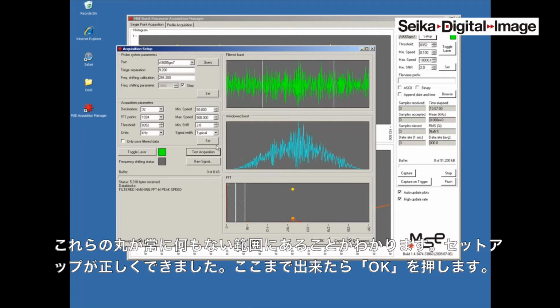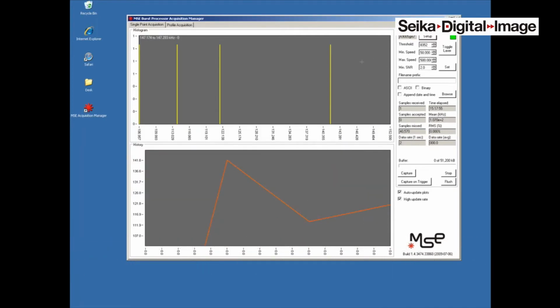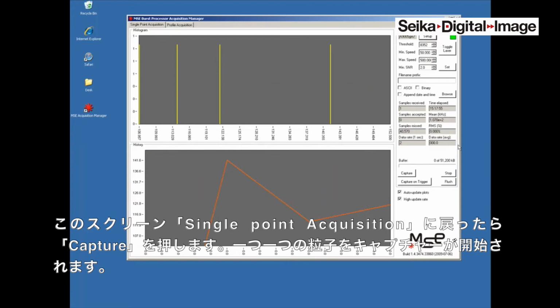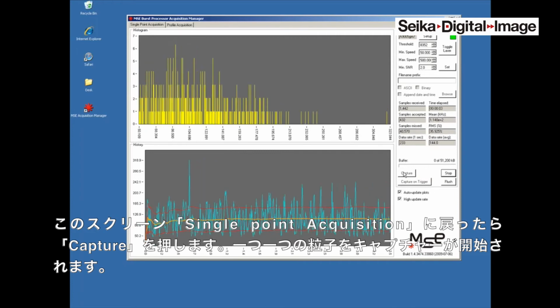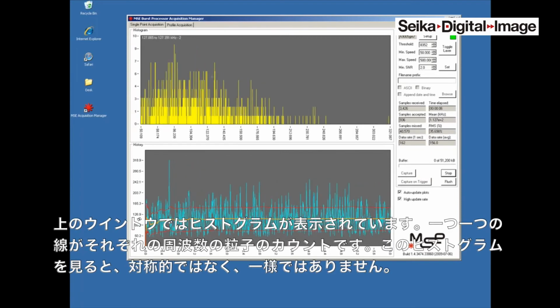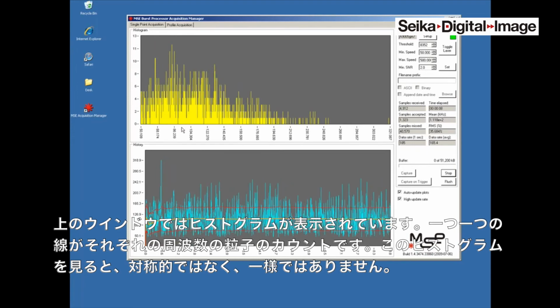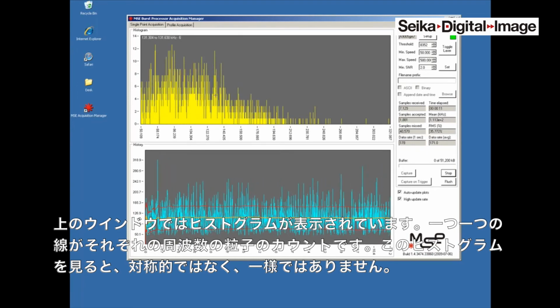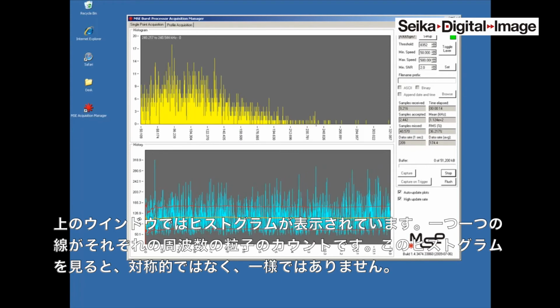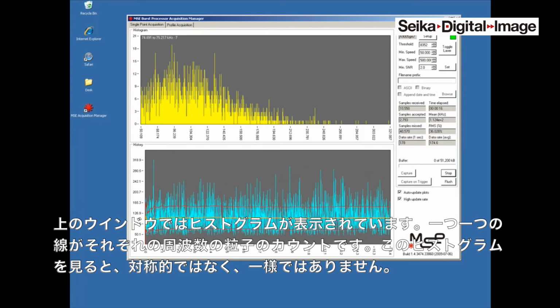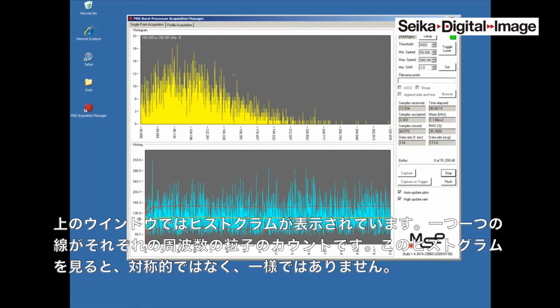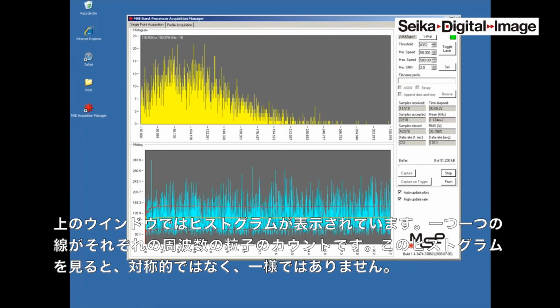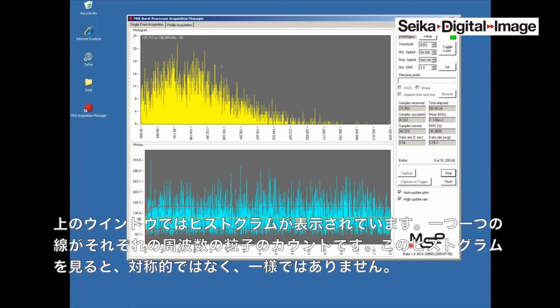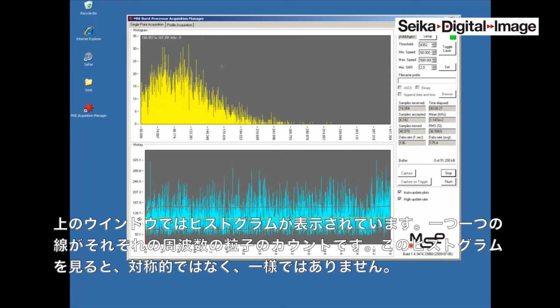So our setup is correct. Once we are happy with this, we push OK, and then go back to this screen to the single point acquisition and do a capture. What it does is capture the individual samples. On top is the histogram. Every single line is one frequency, and as you can see, we are generating a histogram that is somewhat skewed, which usually indicates that the flow is not uniform and also not symmetric.